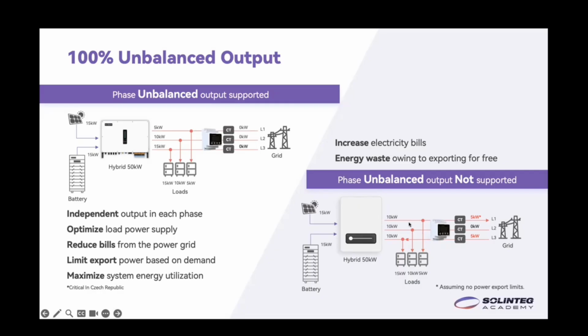Well, for example, let's first take a look at the phase over here. Now the device installed in this phase requires 5 kilowatt power, but the inverter still sends 10 kilowatt power. So in this case, your 5 kilowatt power that has been wasted will be sent to the grid if there is no power export limit. And if we are in some countries where we can send the extra power to the grid and even get some credits, the energy bill will not be that bad. But if we are in some countries that have a power export limit, or we can't get credits when sending the extra power to the grid, that means this 5 kilowatt power will just be wasted.